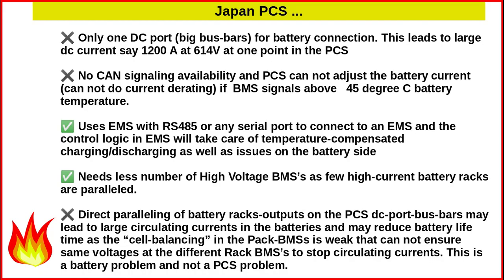Now, one advantage of concentrated current at a single DC port is that we will have fewer racks of batteries and fewer high voltage boxes, which are high voltage BMSs, which are to be paralleled, because the high voltage box is unreliable, and since we will have fewer high voltage boxes, we have an advantage here in the Japan PCS case.